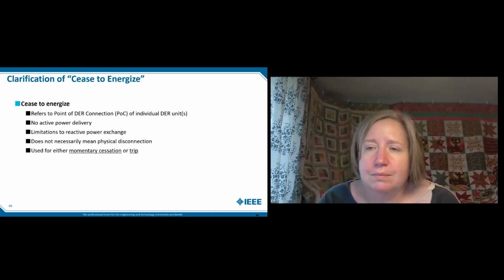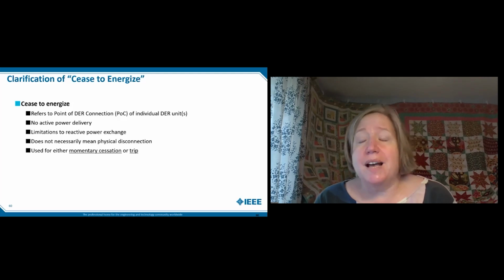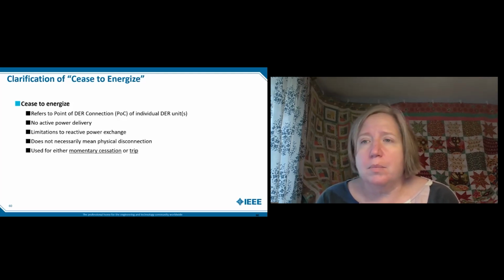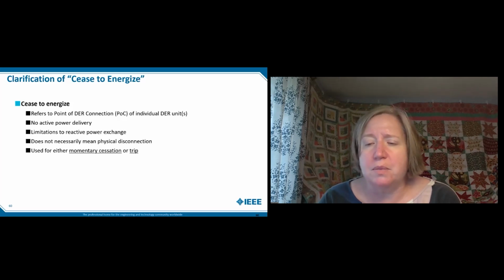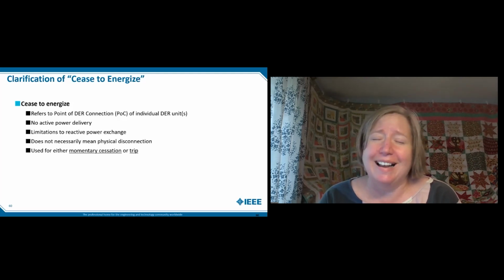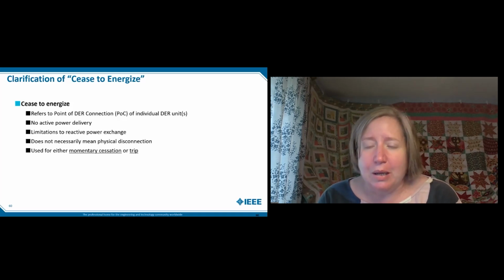And to shift gears, I don't think you can see the comments. We've got one here. What caused the limit on adding more PV due to the feeder you mentioned? It's really the capacity that we can put on the feeder. I forget if we're at 12 or 15 megawatts, but we've already run 795 on the feeder, and we're hitting the limit of the capability of the feeder.